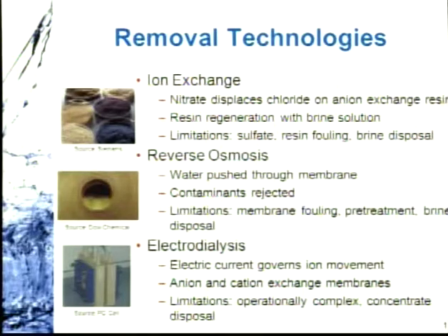The limitation here is that those membranes can foul over time by rejecting all of the nitrate and other contaminants. They're also rejecting other things like the salt that might be in that water to begin with. And some of those salts can build up to the point that they complex with other things in the water, and they will permanently foul the membrane surface with either organic or inorganic fouling that renders those membranes less effective.